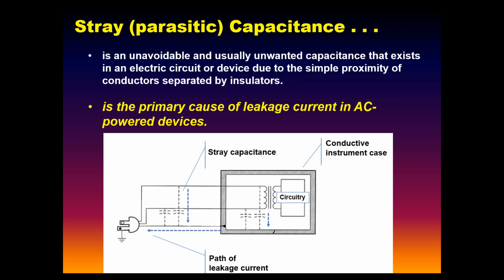These are insulated wires, and we have capacitance here, which has a reactance at 60 hertz that permits currents to flow from the hot side to neutral, or in this case, the ground. This is a metal case, and if it's grounded, we've got capacitance between the hot side of the line and the case, and neutral and the case, even in an unterminated line cord. If you measure the capacitance of an unterminated line cord, say between hot and neutral, or hot and ground, you get somewhere around 10 nanofarads, just from the line cord, with nothing connected. So one of the two reasons we have grounds on these machines is to drain that leakage current away.